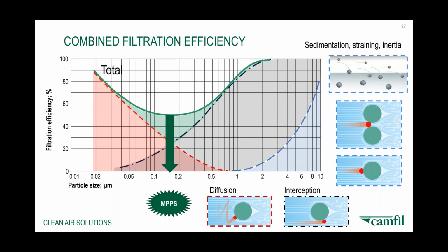And that's what's called in filtration standards or terms the MPPS, or most penetrating particle size. This is the particle size that is most difficult, irrespective of how all of these filtration effects work together, the particle size that's most difficult to get. And the current test standards then say that we must test our HEPA filters at that particle size. So it's a very tough test.